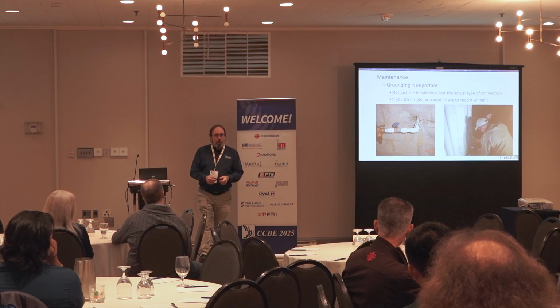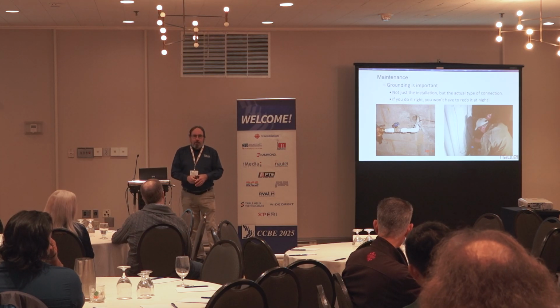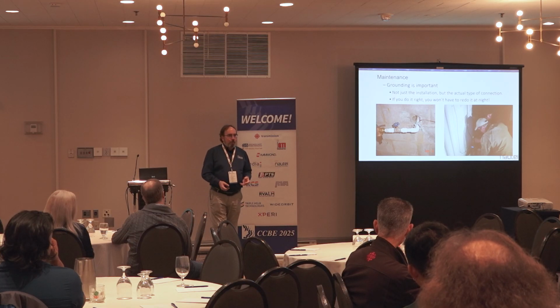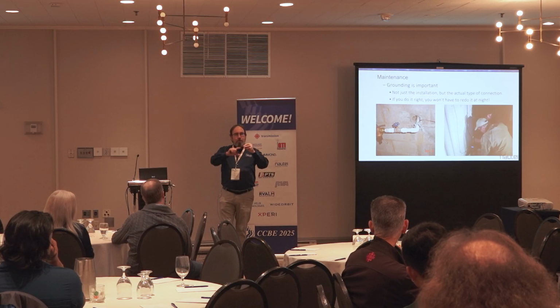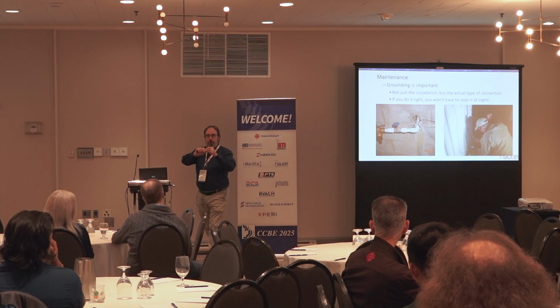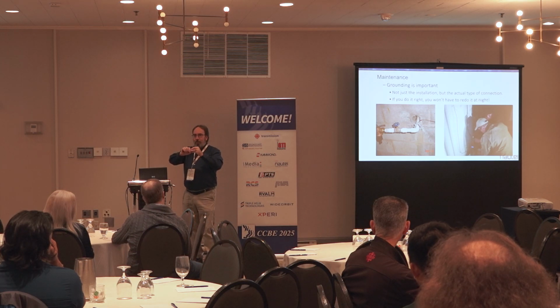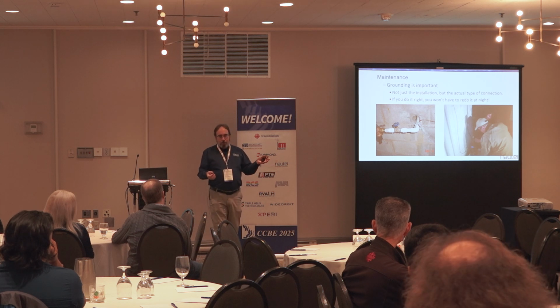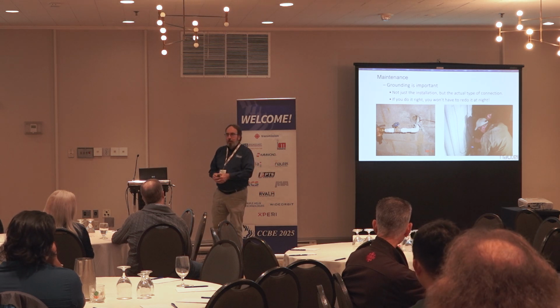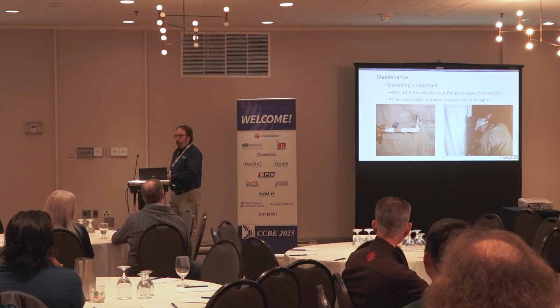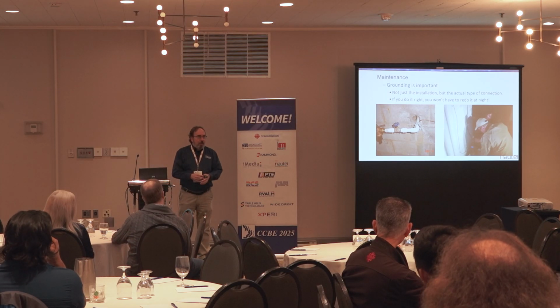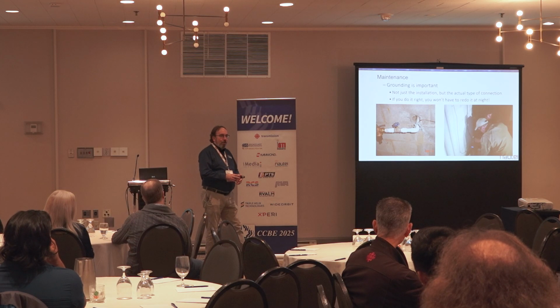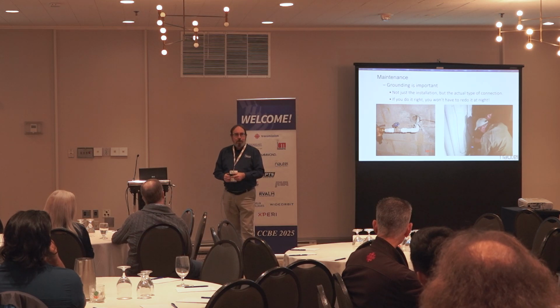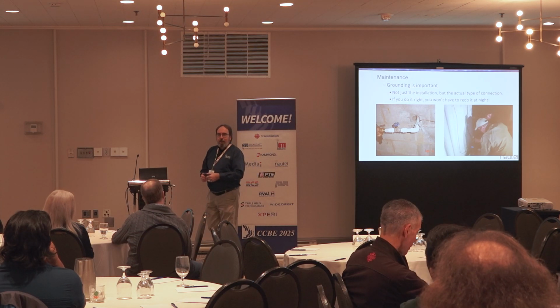I hate compression connections with a passion. Copper is malleable, and it will compress in a compression connection and deform to displace air, and as it does that, it will get loose. If you put stranded or even solid wire in a compression connection, come back a week later and tighten it down, a month later tighten it down, a year later tighten it down, and maybe then you can walk away from it. Hate them, hate them, hate them.